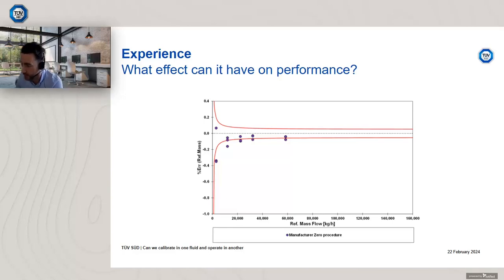Now, why is this important? I'm trying to show you where the zero has an effect. You can see the meter manufacturer specification in red. You can see that some of the data points still sit outside when you do repeat points, and that's because of the effect that zero can potentially have on your meter's performance.